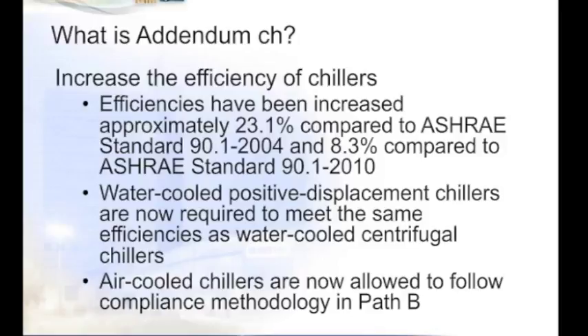Besides increasing chiller efficiencies, the addendum will require positive displacement water-cooled chillers to meet the same efficiency requirements as water-cooled centrifugal chillers. So now reciprocating, screw, and scroll compressors have the same efficiency requirements as centrifugals. The other important item to note in this part is that air-cooled chillers are now allowed to follow compliance methodology path B. Pat will explain this compliance path in more detail later.